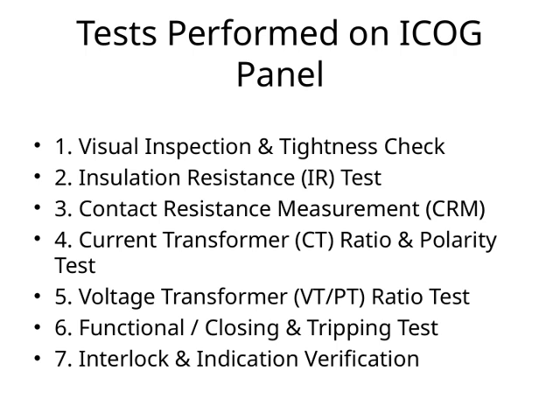After that, we perform the current transformer ratio and polarity test. This helps us verify that the CTs are providing accurate current readings and are correctly wired, which is vital for precise measurement and protection functions. Following this, we conduct the voltage transformer or VT-PT ratio test. Similar to the CT test, this ensures that the voltage transformers are functioning correctly, providing accurate voltage measurements needed for system monitoring and protection. The next step is the functional, closing, and tripping test.